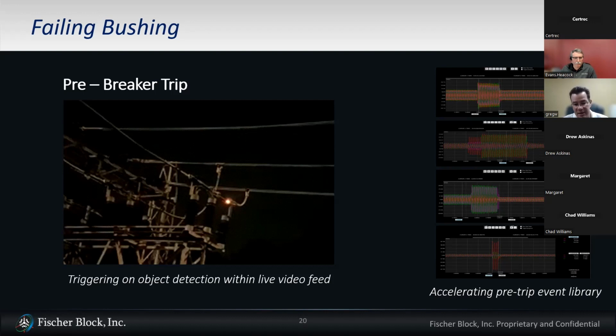And when those conditions are sensed in the video feed, WaveIQ will synchronously trigger our smart blocks to capture electrical signals at the local substations, so that we're able to now build our pre-trip event libraries, electrical signature libraries, at an accelerated rate. We don't have to wait for breaker trip to get a signature to put in the library. So we're building our libraries now for this application such that our platform can then sense and predict that arcing and hotspots are happening in areas where we don't have a video feed. And so it's very exciting for us to be working on this technology, and we're working with some utilities that are dealing with wildfire issues and arcing issues and hotspots and substations for predictive analytics.